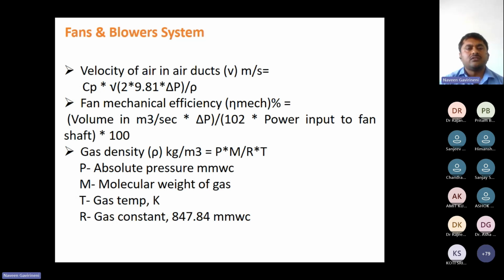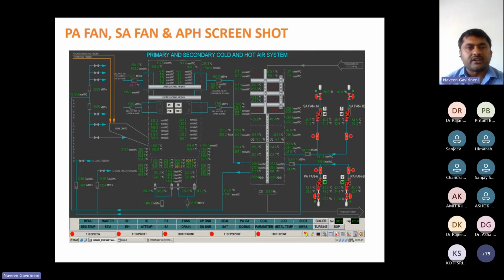So this is the velocity of air calculation, and this is the formula for that. This is the mechanical efficiency calculation: volume into delta P, divided by 102 into power input. These are the most important things to calculate fan performance. Then the density of gas, as we know, comes under this. This is the screenshot for our plant.